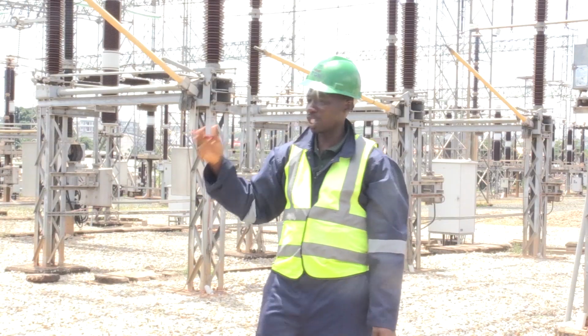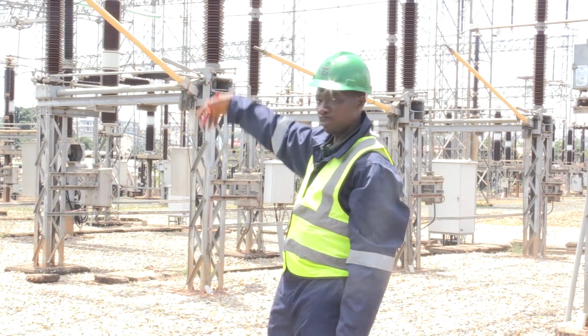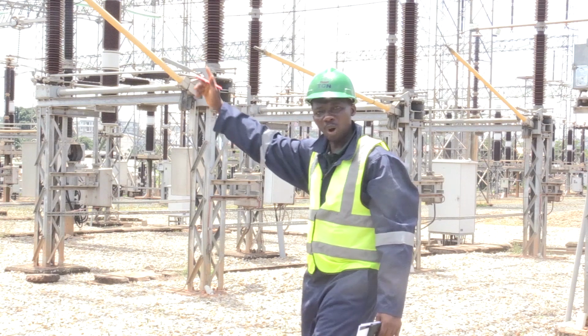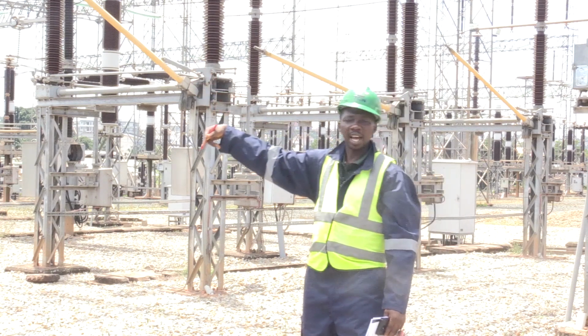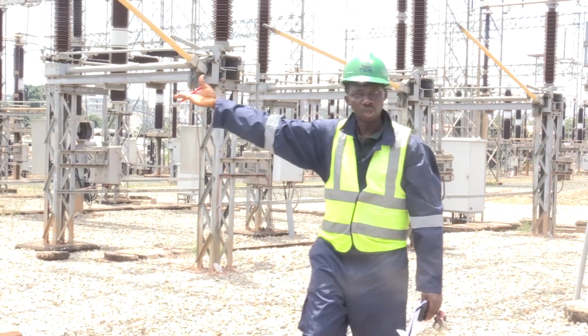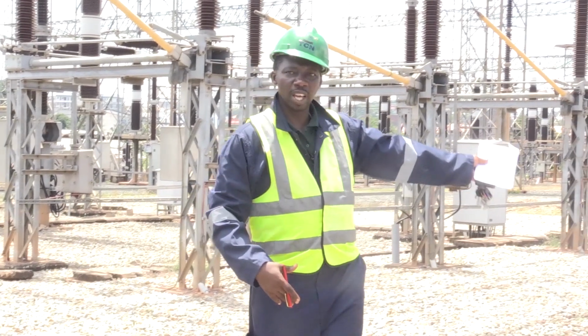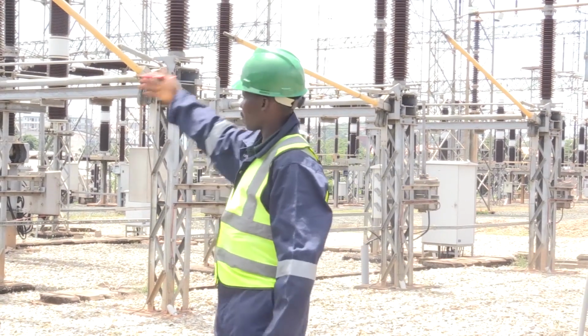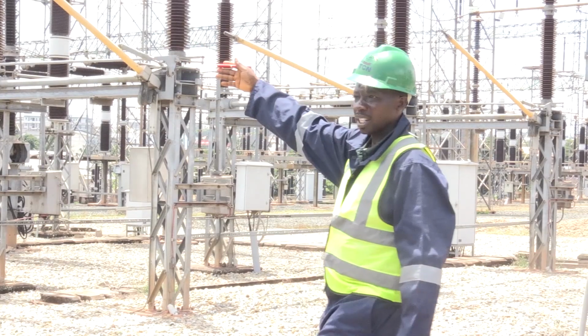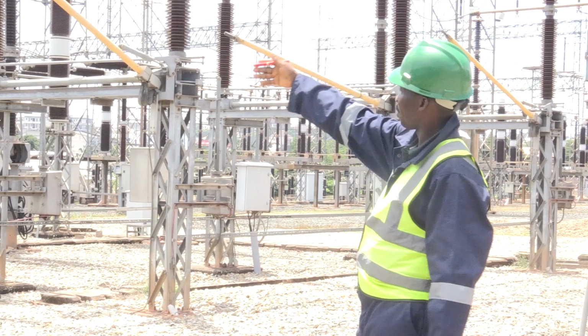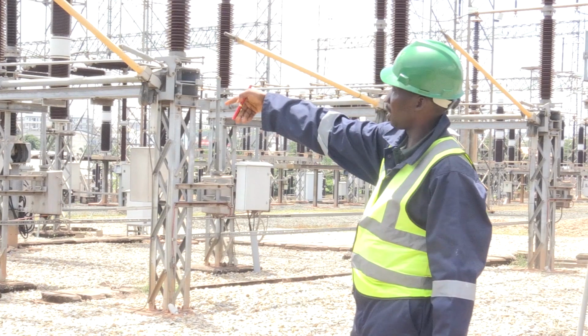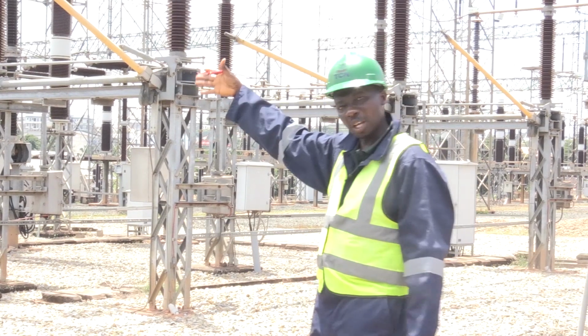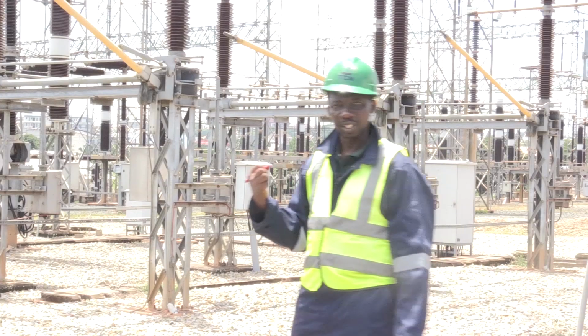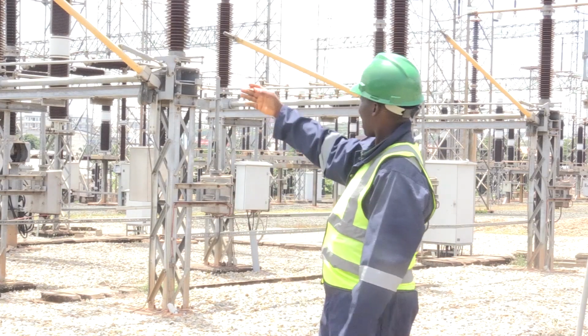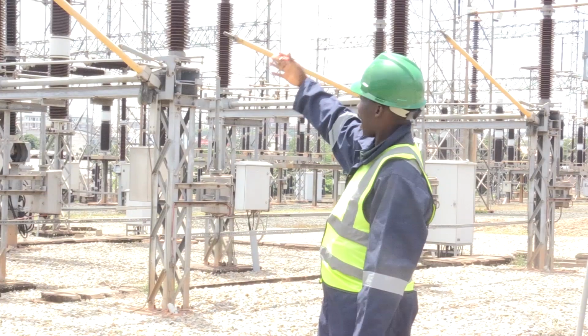When it gets to this point, remember we have opened the Onitsha line, so what we now need to do is close either Ugwaji 1 or Ugwaji 2 and get energy here, and then it drops at the gantry there. We have the VT right there to take measurement of what we are receiving, and then it transverses to the bus, and comes down to this place.